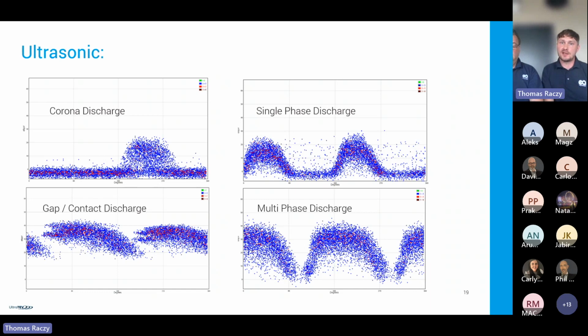On the right-hand side, top and bottom, we've got single and multi-phase discharges. With single phase discharge, as you can appreciate, there's clear separation, 180 degrees, and the off time when the discharge is not occurring is much longer. On the multi-phase discharge, where the discharge occurs between two phases, the inception window is much wider, so the PD happens over a wider part of the cycle, because both phases are discharging at the same time.